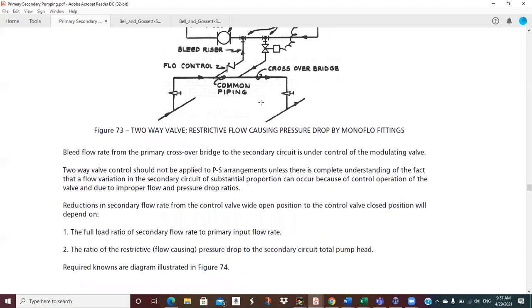Reductions in secondary flow rate from the control valve wide open position to the control valve closed will depend on these two factors, these two ratios. The full load or design ratio of secondary flow rate to primary input flow rate. So you take your secondary flow rate and you take your primary flow rate and you calculate the percent, as we'll see here in a second.